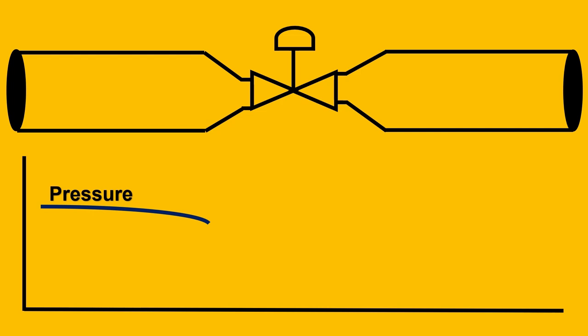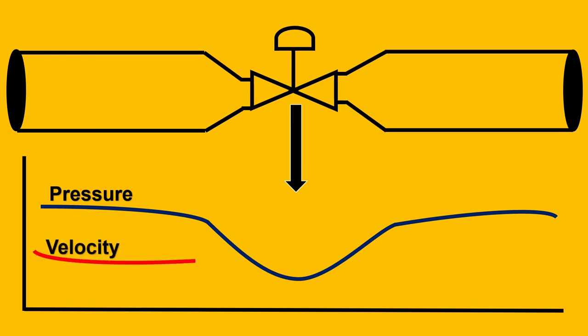So, initially the pressure is high then across the valve the pressure is going to drop and eventually some of it will get recovered. On the opposite side what is going to happen to velocity as the law of conservation of energy says when the pressure is high the velocity would be less. As the pressure drops the velocity is going to increase and eventually as the pressure is recovering the velocity is going to reduce.